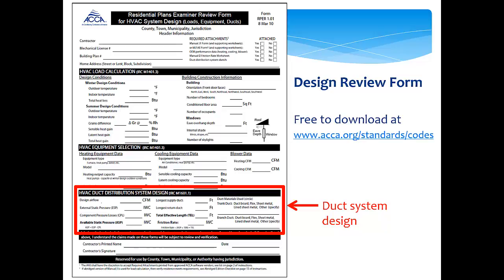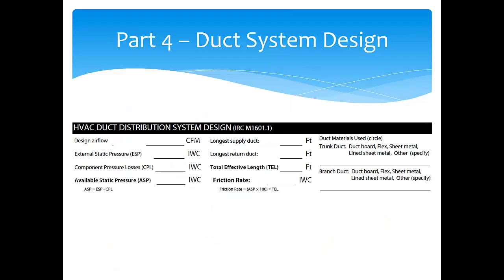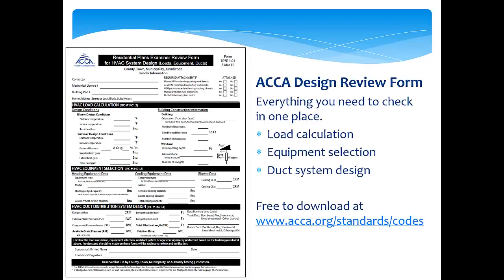The duct sizing portion of the design review form has a place for all six verification points: design airflow, external static pressure, sum of component losses, available static pressure, total effective length of the longest system path, and the calculated friction rate. The designer can also specify the duct material used. This form is available to you for free — just visit ACCA's codes page at acca.org/standards/codes.